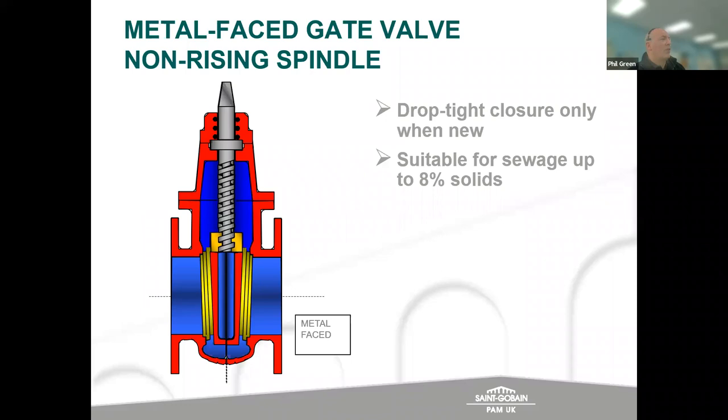damage the surface of this valve. So you might get a very small seep of fluid coming through this. So it's not drop tight after the first use. It can be used for solids, sewage with up to 8% solids. So it's a fairly wide ranging use.